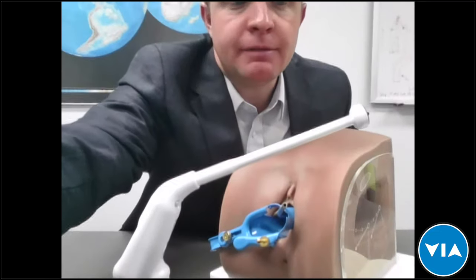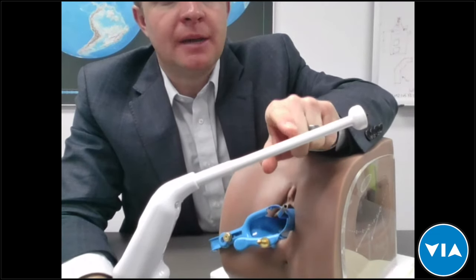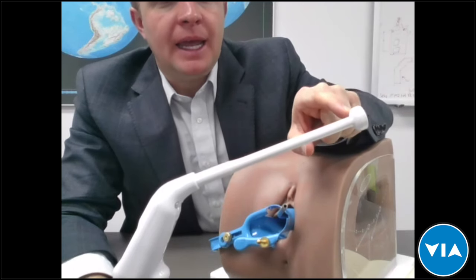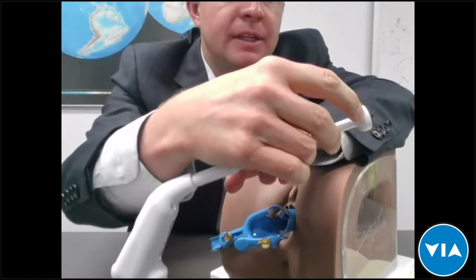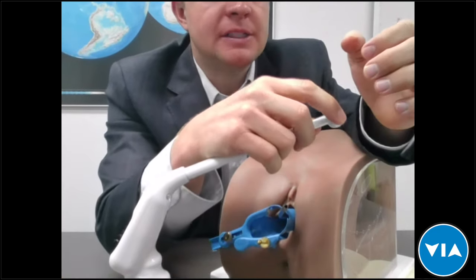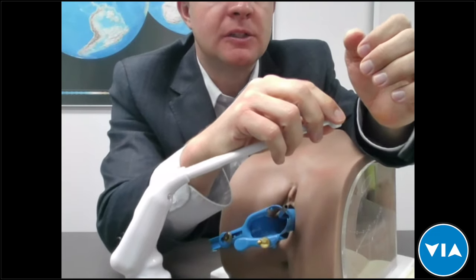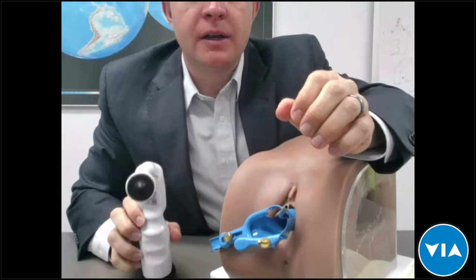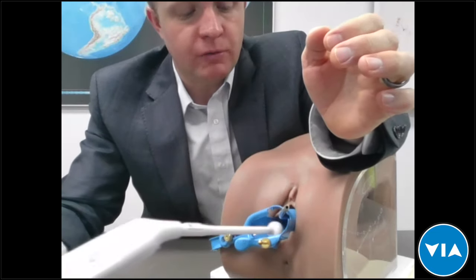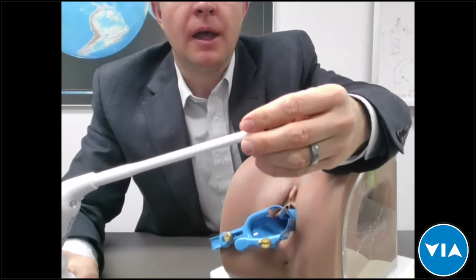During design and development, we took temperature readings along the shaft of the probe and at the bell — the bell-shaped area of the probe. The temperature on the side of the bell doesn't get above 43 to 44 degrees Celsius. The heat is concentrated on the black tip, and even if the side were accidentally touched, it feels warm but is not hot to the touch — there's no burn reaction.